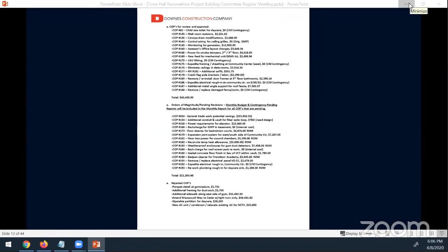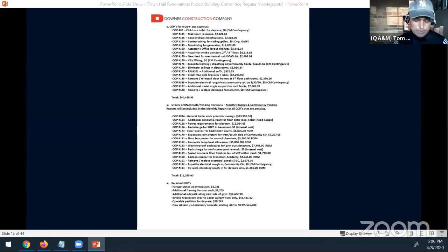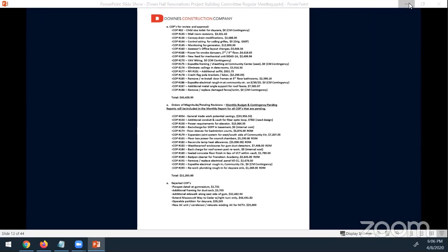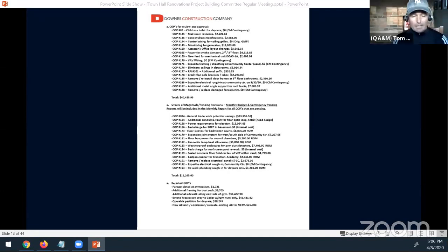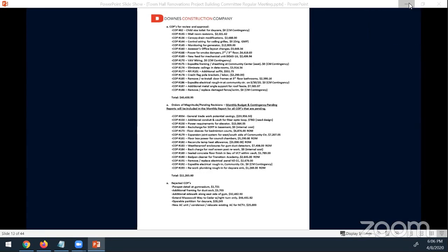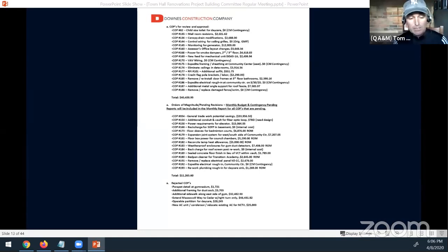So the generator itself, everything that's on the generator uses by calculation 87% of the generator's capacity. The recommendation is to be in the range of 82%. The engineers indicate that realistically, the actual load on the generator is going to be less than 87% because not everything is used and plugged in all at once.